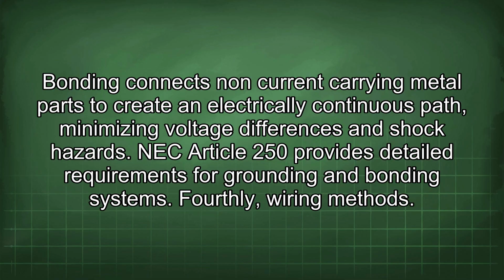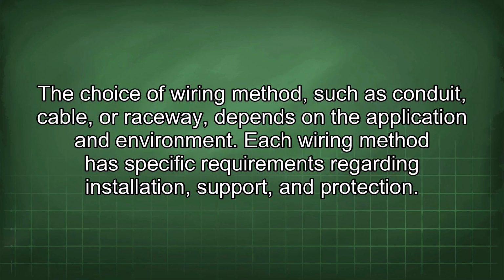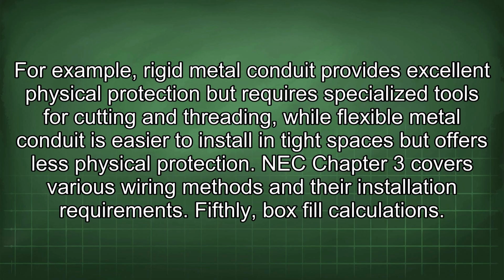Fourthly, wiring methods. The choice of wiring method, such as conduit, cable, or raceway, depends on the application and environment. Each wiring method has specific requirements regarding installation, support, and protection. For example, rigid metal conduit provides excellent physical protection but requires specialized tools for cutting and threading, while flexible metal conduit is easier to install in tight spaces but offers less physical protection. NEC Chapter 3 covers various wiring methods and their installation requirements.